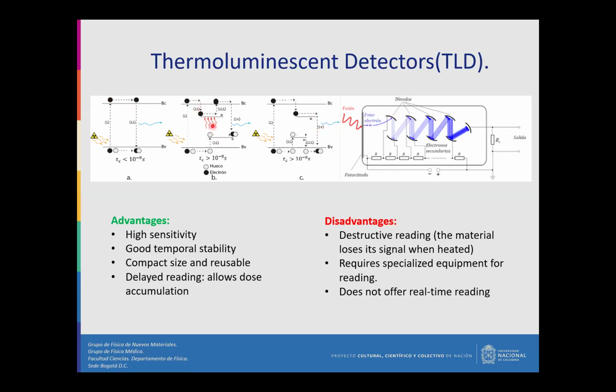So when I have this effect, the electrons that dropped and remained in these middle levels are taken to the conduction band, and after a little time, like nanoseconds, they fall to the levels so close to the valence band, and they recombine and generate a photon. This falling of the electrons and recombination creates a photon that I need to take with another piece of equipment to take that signal. Okay, the light is detected and quantified, and this intensity is proportional to the absorbed radiation dose. Thus, the TLD doesn't directly measure the radiation, but the effects of radiation on the material, through the released light signal. Okay.